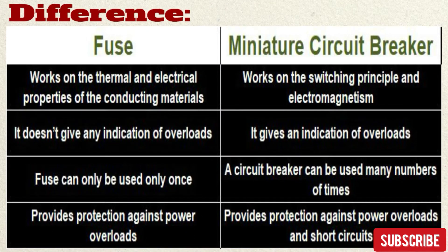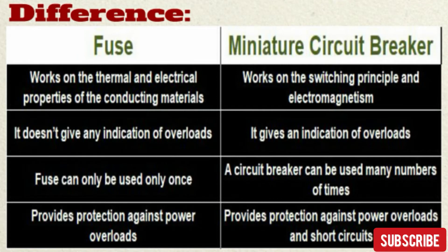Now let's look at some differences between fuse and MCB. First, a fuse works on the thermal and electrical properties of conducting materials, but an MCB works on the switching principle and electromagnetism. Second, a fuse does not give any indication of overloads, but an MCB gives an indication — if any fault occurs in an electrical circuit, the MCB will automatically trip, so you can easily identify which circuit has the problem by checking the panel.